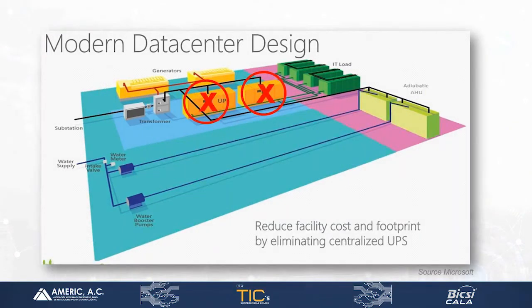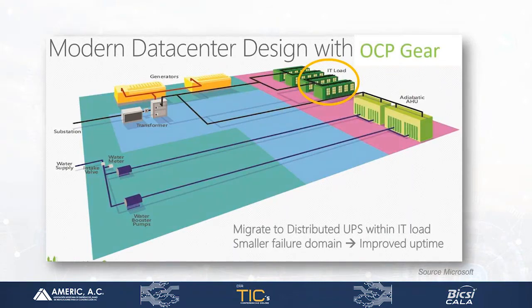We take them out. And then we take out the centralized UPS - we don't use it. We do it differently: in the IT racks, we embed lithium-ion battery backup units in the IT load racks to do the UPS function.